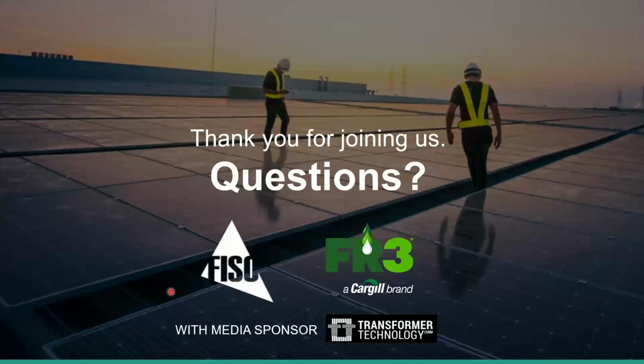Yes, we have made several tests on FR3 fluid, on aging vessels, sealed vessels tests, and we have monitored all the properties of FR3 fluid in contact with materials that are usually used inside the transformers. And for example, the question was related with permittivity, and you can say that permittivity remains stable during the complete lifetime of the test and the process of the transformers. And regarding the other properties, talking tangent delta and this kind of measurements that are made on the transformer, we didn't see differences on the normal behavior with mineral oil.